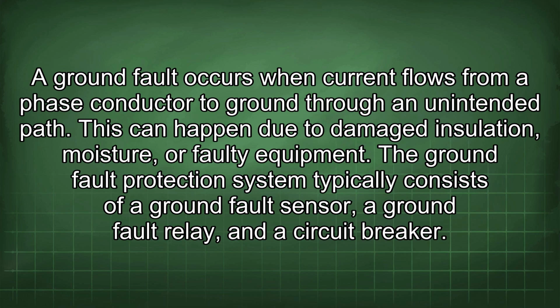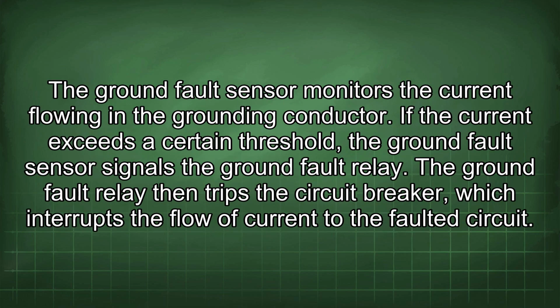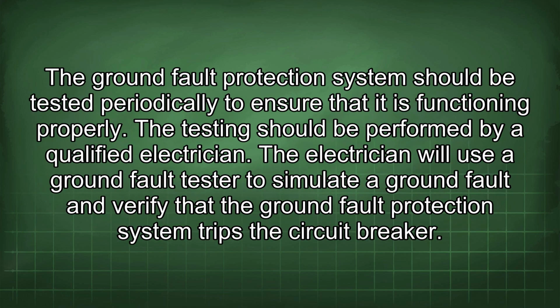The ground fault protection system typically consists of a ground fault sensor, a ground fault relay, and a circuit breaker. The ground fault sensor monitors the current flowing in the grounding conductor. If the current exceeds a certain threshold, the ground fault sensor signals the ground fault relay. The ground fault relay then trips the circuit breaker, which interrupts the flow of current to the faulted circuit. The ground fault protection system should be tested periodically to ensure that it is functioning properly. The testing should be performed by a qualified electrician. The electrician will use a ground fault tester to simulate a ground fault and verify that the ground fault protection system trips the circuit breaker.